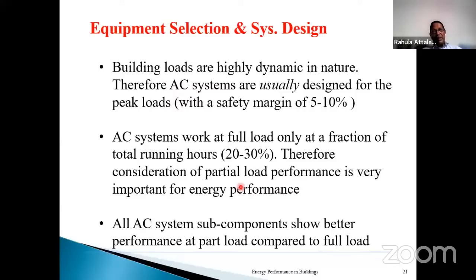So that means that if you just try to meet the capacity to just meet the requirement, not slightly allowing leverage of load slightly above the requirement, it will not be in a zone of 60 to 80%. Let's say 60 to 80% is arbitrary, but in that range, it will depend on what the type of equipment is. So in addition, we also have a 5 to 10% margin kept for calculation. So in general, it's not much of an issue trying to slightly oversize, so that in actual operation, it will operate not at the full load, but in the part load condition.